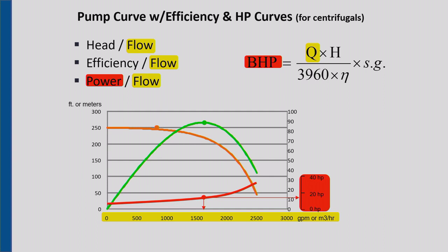And then from there, if I open up the valve some more and let some more liquid go out, notice the efficiency starts falling off. You get more flow, you get less head, but the efficiency is dropping. That's where everything in the pump is happy, right at that best efficiency point. That's where you'd like the pump to run. Okay?